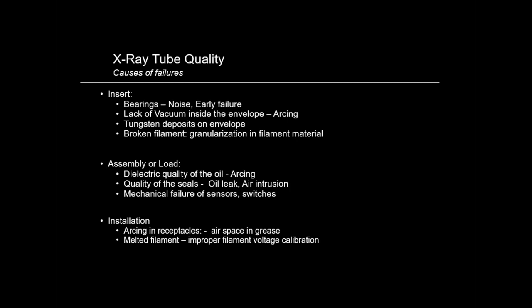You can have this dielectric quality of oil can create arcing, which is what we were just talking about, the oil. You can have an oil leak or air intrusion. You get a bubble inside that tube, arc. You can get the mechanical failure of sensors, number of sensors, pressure sensor, temperature sensor, depending on the architecture of the system, architecture of the tube. You can have a short in one of those, cause problems with your installation. Again, these are assembly or manufacturing problems.